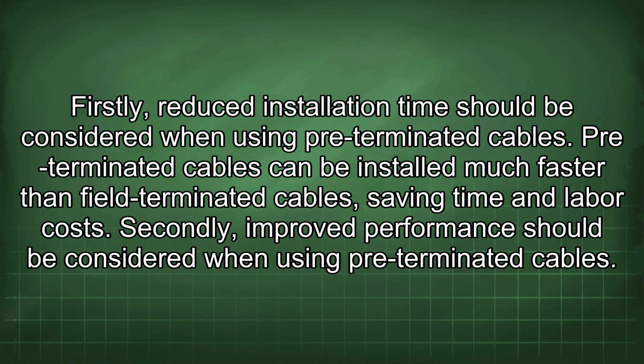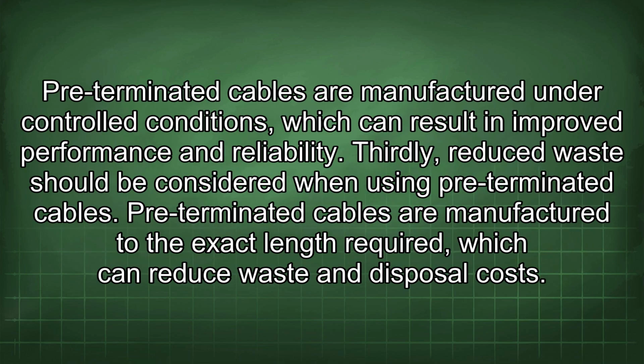Secondly, improved performance should be considered when using pre-terminated cables. Pre-terminated cables are manufactured under controlled conditions, which can result in improved performance and reliability. Thirdly, reduced waste should be considered when using pre-terminated cables. Pre-terminated cables are manufactured to the exact length required, which can reduce waste and disposal cost.